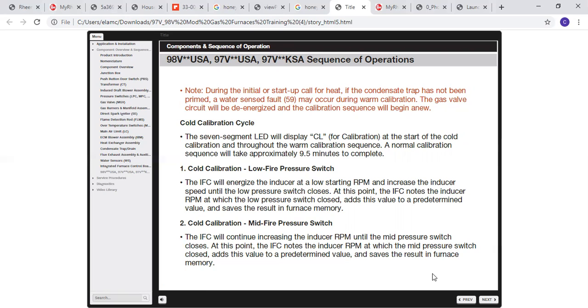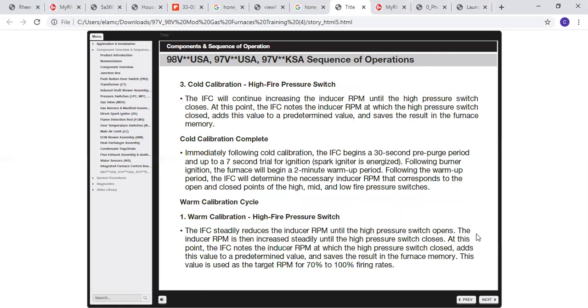Next, it'll go into the mid pressure switch. It will continue to increase the RPM until the mid pressure switch closes. At this point, the IFC notes that RPM value, adds that to the predetermined value, and saves the result into the furnace memory. Next step in the cold calibration, it will keep increasing the RPM until the high pressure switch closes. At this point, the IFC notes that inducer RPM value, adds that to the predetermined value, and saves that into the memory. After that, the cold calibration is complete.